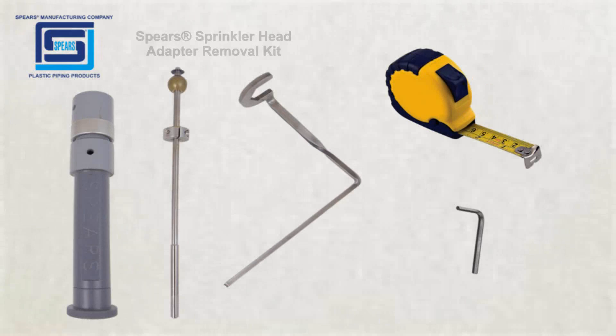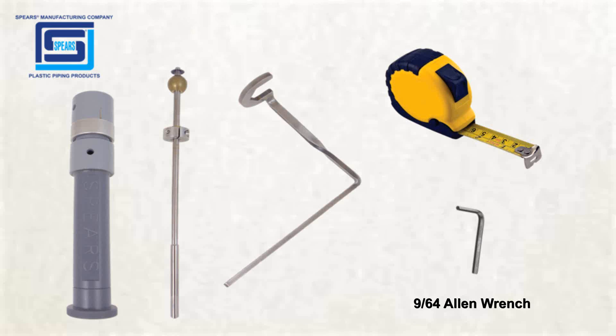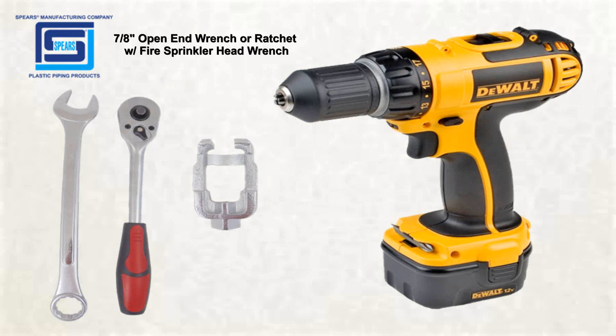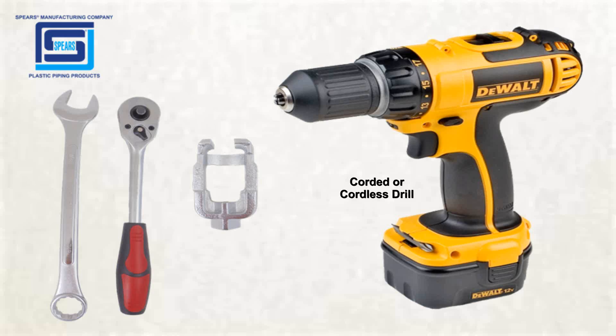For this procedure the tools that you will need are the Spears Sprinkler Head Adapter Removal Kit which includes a deburring tool, an inside pipe cutter, and a head adapter backup wrench. You will also need a tape measure, a 9/64 Allen wrench, a 7/8 inch open end wrench or a ratchet with a fire sprinkler head wrench, and either a corded or cordless drill.